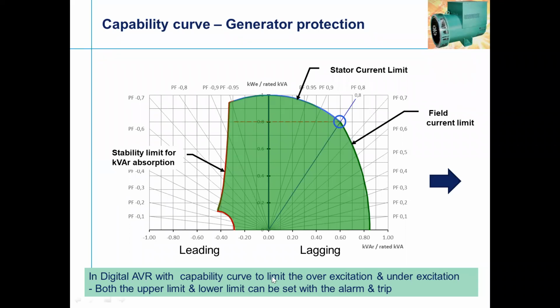This is very, very important, which generally has not been discussed in the field. Capability curve. For any selection of your load with respect to your demand on the generator, on a bigger one megawatt and above, please refer to the manufacturer and take this capability curve. With respect to that you have to go for a selection, and the manufacturer will give the right setting point for this 3-point check.